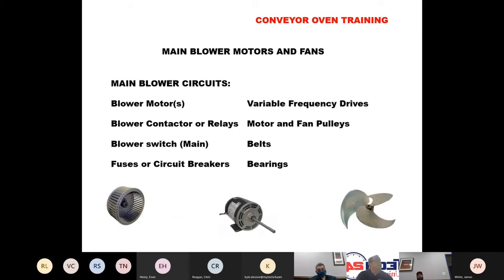So first, main blowers and fans. There's several components you're going to find depending on which manufacturer you're dealing with. Your blower may be started by a contactor or a relay. Unless you have a digital control, you may have a blower switch that turns on the main blower. There are typically going to be some sort of fuses or circuit breaker protection in the motor circuit that may cause issues. Newer ovens, we're seeing variable frequency drives that are running the motors.